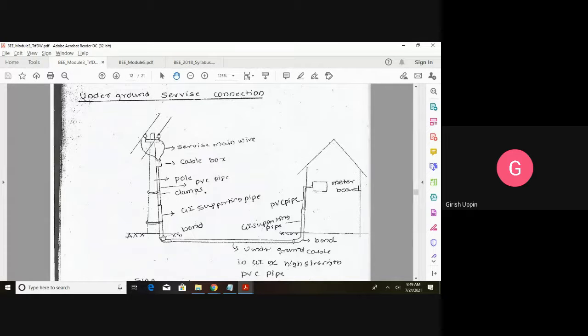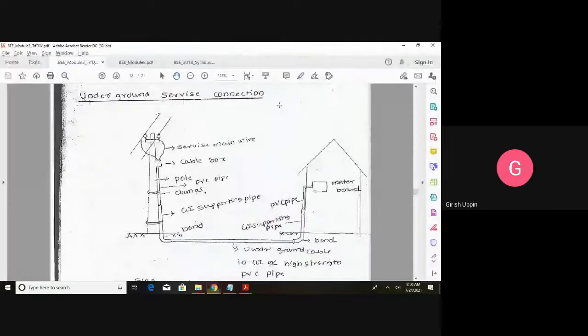So they will dig the ground about 2 feet or 2.5 feet, and inside the ground we put a GI pipe, galvanized iron pipe. Inside the GI pipe, the cable will go. So this is the GI pipe what you are seeing. Inside the GI pipe, the cable will go, and then it will come out on the other end. We will have the bend, using the bend, and that is also a GI pipe or PVC pipe.